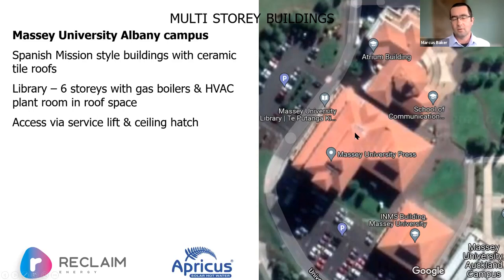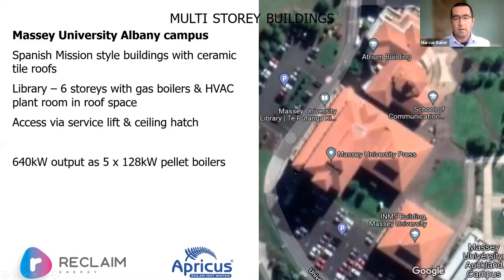And yeah, you're not getting anything in there except if it goes up through the service lift, and then there's a hatch, and there's a gantry to hoist it up. But the issue, of course, is that with 600 kilowatts or so of load, that's a significant amount of pellets. And we can't blow them through the standard delivery truck up to here. And even if we could, the many tons of pellets you'd want to have on hand for use wouldn't be conducive to a six-story plant room when you start talking to the structural guys.